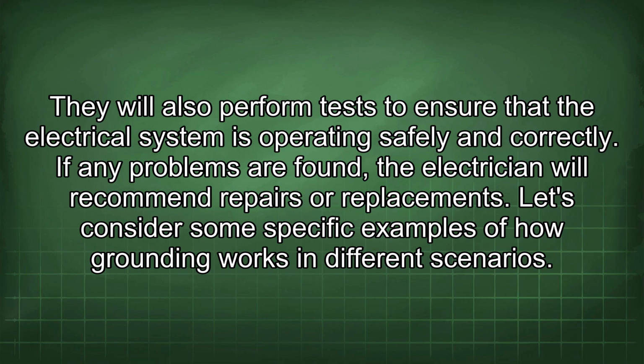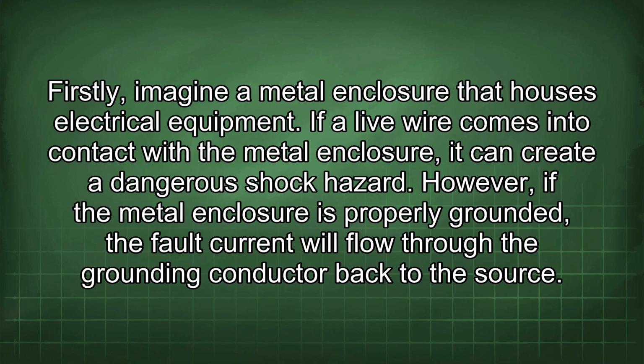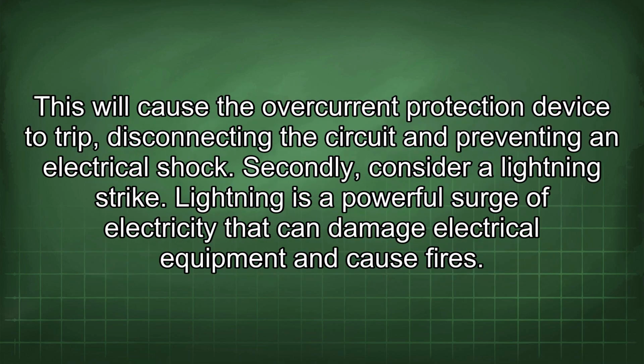Let's consider some specific examples of how grounding works in different scenarios. Firstly, imagine a metal enclosure that houses electrical equipment. If a live wire comes into contact with the metal enclosure, it can create a dangerous shock hazard. However, if the metal enclosure is properly grounded, the fault current will flow through the grounding conductor back to the source. This will cause the overcurrent protection device to trip, disconnecting the circuit and preventing an electrical shock.